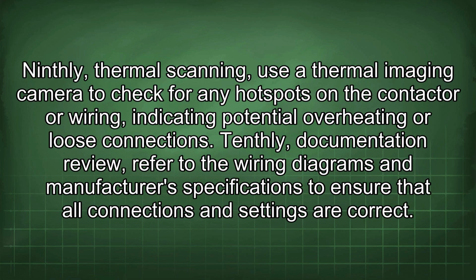Ninthly, thermal scanning. Use a thermal imaging camera to check for any hotspots on the contactor or wiring, indicating potential overheating or loose connections. Tenthly, documentation review. Refer to the wiring diagrams and manufacturer's specifications to ensure that all connections and settings are correct.